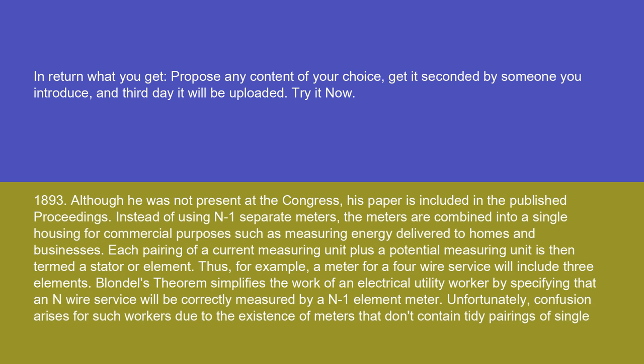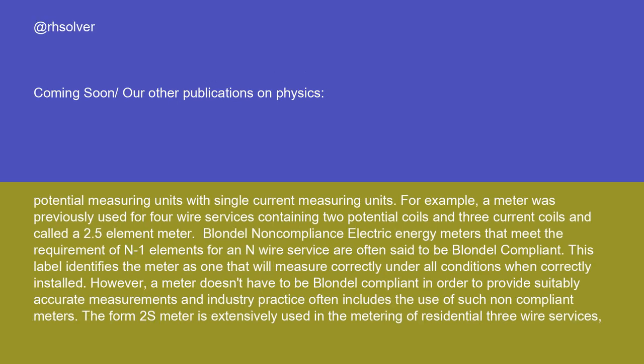Unfortunately, confusion arises for such workers due to the existence of meters that don't contain tidy pairings of single potential measuring units with single current measuring units. For example, a meter was previously used for four-wire services containing two potential coils and three current coils, called a 2.5-element meter. Meters that meet the requirement of N-minus-one elements for an N-wire service are often said to be Blondel compliant.